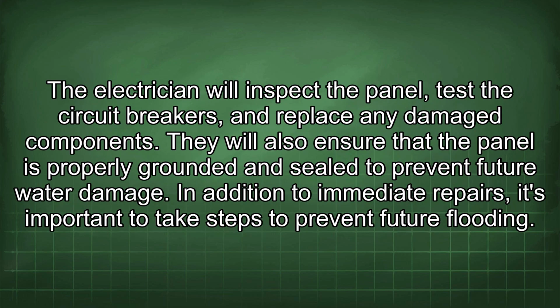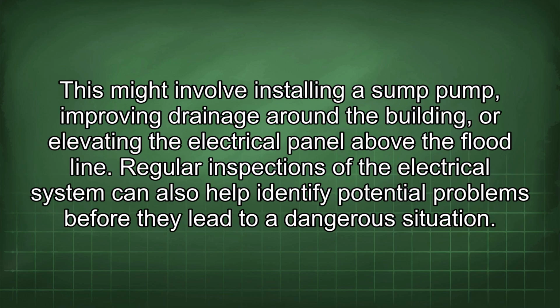The electrician will inspect the panel, test the circuit breakers, and replace any damaged components. They will also ensure that the panel is properly grounded and sealed to prevent future water damage. In addition to immediate repairs, it's important to take steps to prevent future flooding. This might involve installing a sump pump, improving drainage around the building, or elevating the electrical panel above the flood line. Regular inspections of the electrical system can also help identify potential problems before they lead to a dangerous situation.